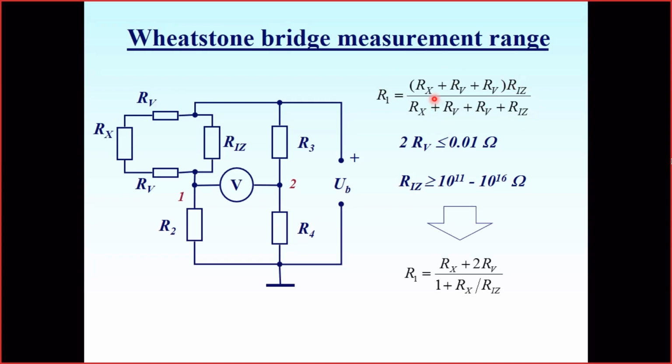So we know how to calculate the total parallel resistance. It is R isolated times R series, divided by the sum of the resistance of all the series plus the resistance of isolation. So this is an equivalent resistance, the actual resistance between these two points. The resistance R1 is what will be balanced in the bridge, independently of what is actually inside the bridge.